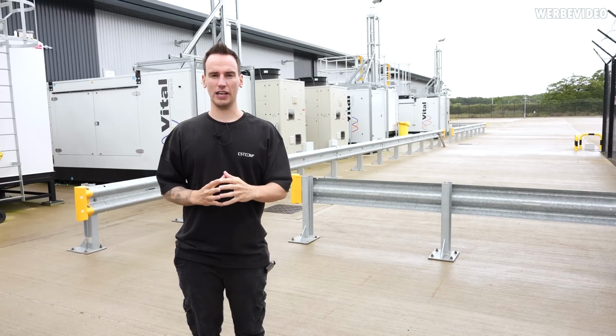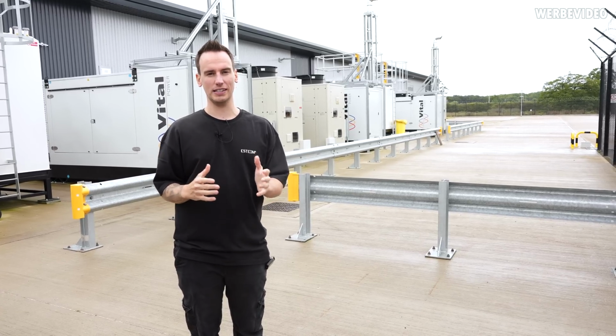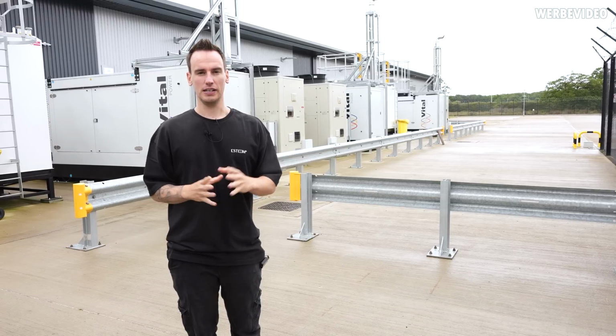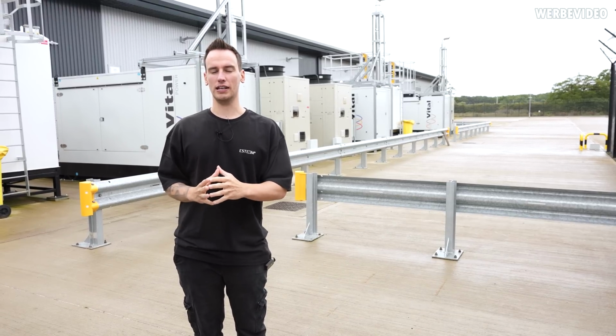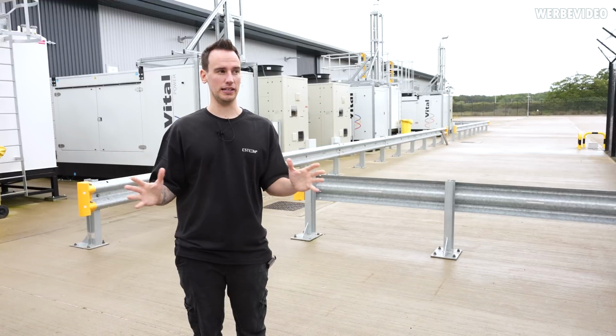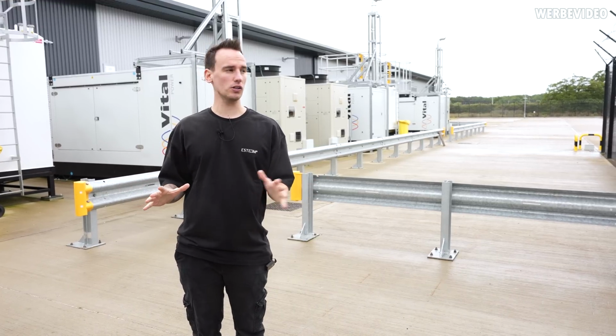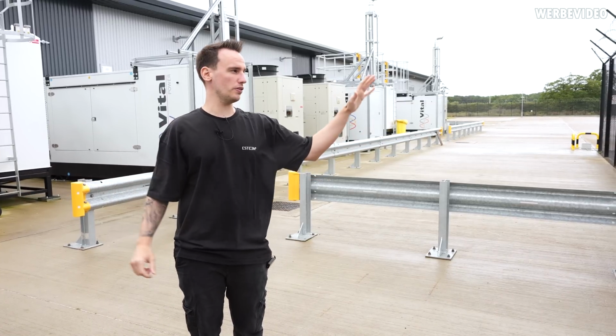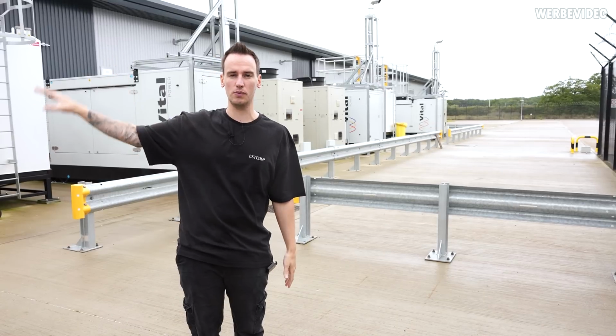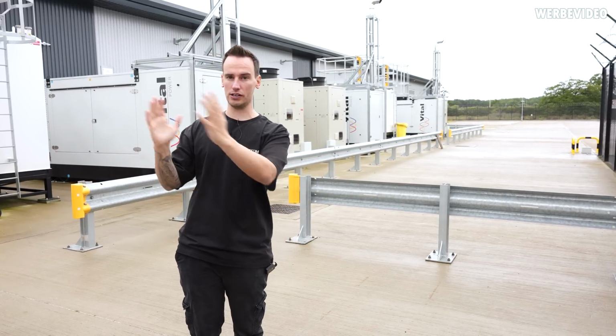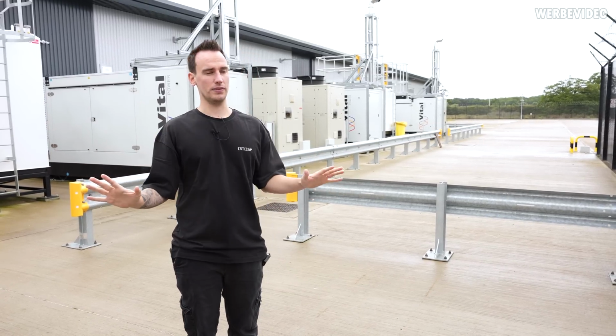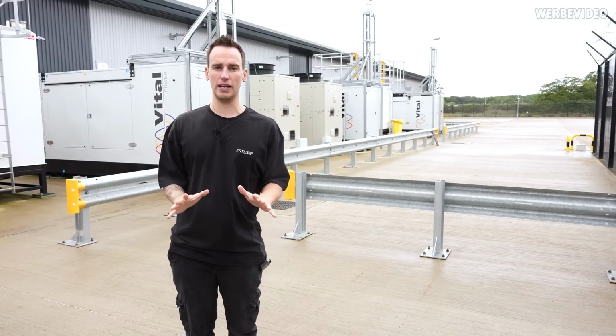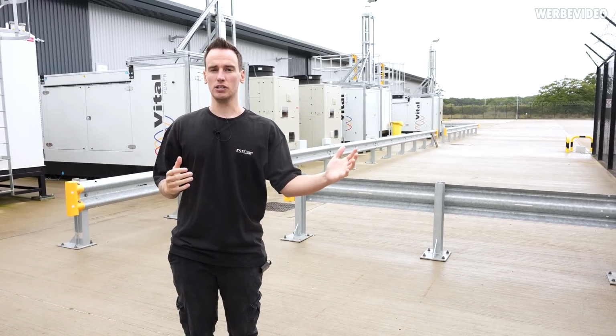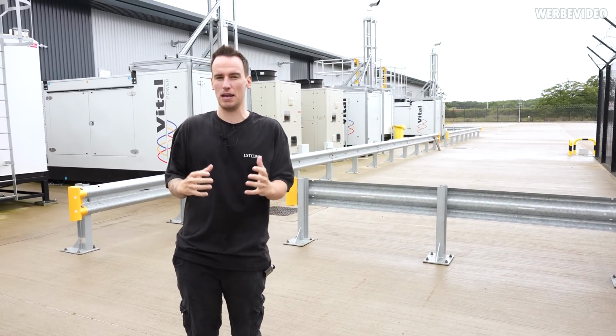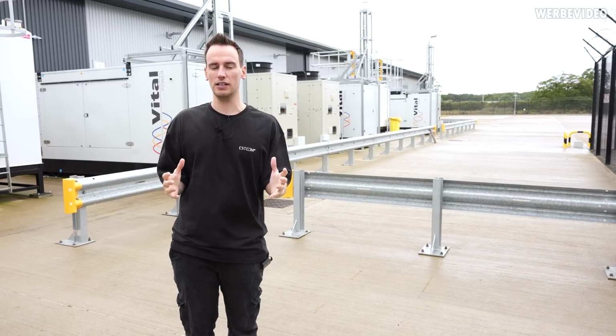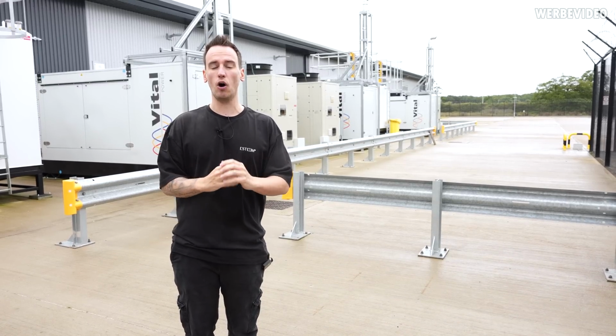This tier 4 certification, what I talked about earlier with this 99.995 availability, is something you can only get if you can maintain full availability, and that starts with the infrastructure. That's also why everything which we see right here with the circuit breakers and then starts with the transformers, all of this also exists on the other side of the building, again full scale. This will be from a different energy supplier with a different power line and everything, to make sure that if something happens that's maybe not even related to the data center, then they can make sure that they always have power.